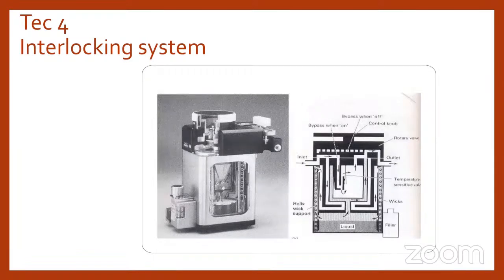Excuse me. So it has an interlock basically to avoid simultaneous use of two vaporizers at the same time. I mean, it has an interlock where only one vaporizer will be available at a time. So we can use either isoflurane or sevoflurane. Any one of the vaporizers, the second will be automatically shut down, so that two agents will not be mixed together to be delivered to the patient in the fresh gas.